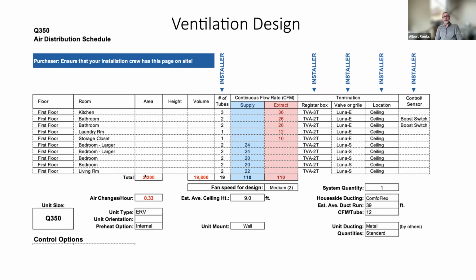We're generally going to want 20 CFM continuous at a minimum in that application. It could go a little higher. 24 is what's listed here. That's a great number. Another larger bedroom, that would be another 24 CFM continuous. A single occupant bedroom could be somewhere between 12 and 20 CFM. It's an 8 CFM difference. That's not a huge number either way. And then 22 in the living room. And so a total is 110 CFM.